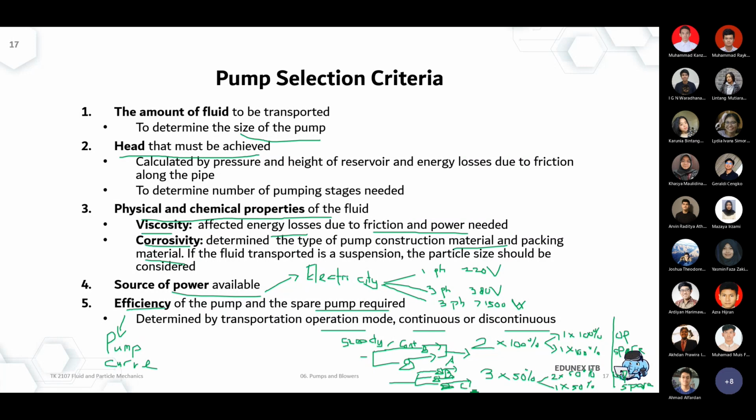A and B work almost all the time. When one breaks down, then you use B and C, and A is fixed by the technician. A is running normally again. Now B breaks down, then you work with A and C. 50% means that's working at 50% of the maximum capacity required. So that's 100% over here, and 100% over here. That's for a steady state operation.